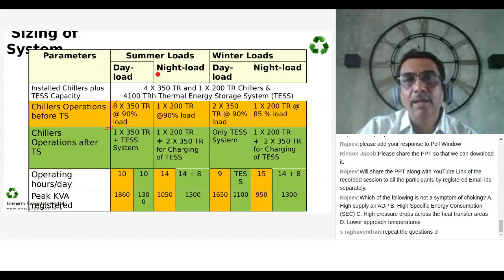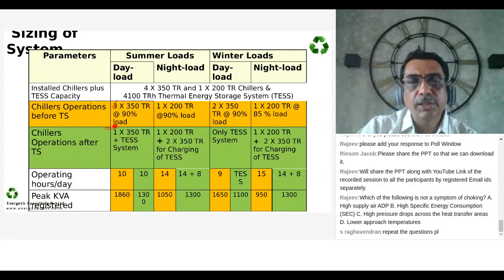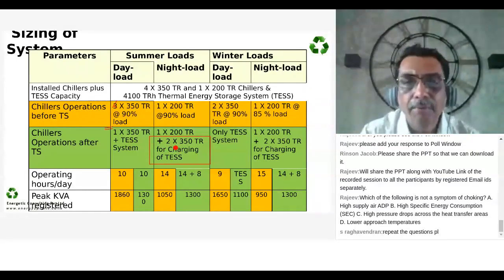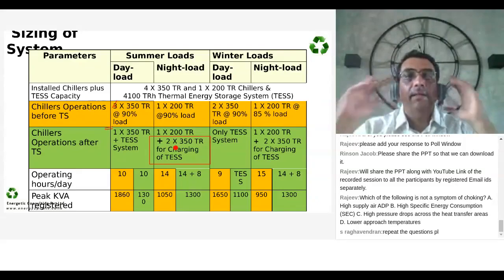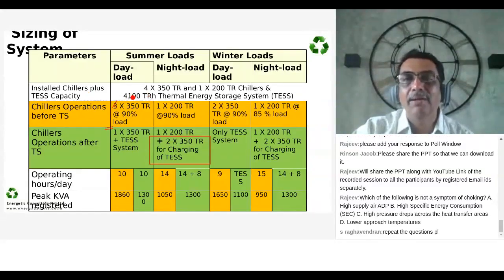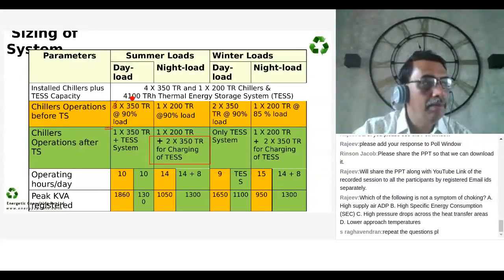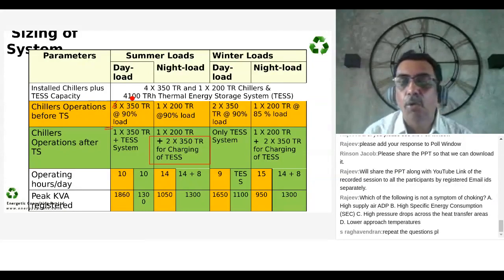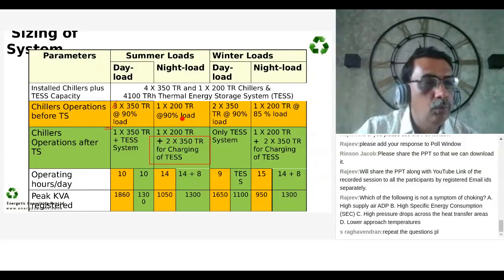Now, what happened during the night load? Those 2 which stopped here actually operated here. Can you see this? These 2 chillers which stopped here during the day started to operate during the night at a lower load and kept on charging the system. You see, 4,100 TR-hour system, not small. So you take it on an 8 hours basis, it was like a 400 TR system. 400 to 450 TR is the average load for charging. So these 2 chillers, 700 TR capacity, operated at 450 TR output to charge the system.